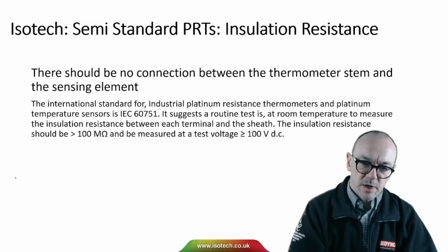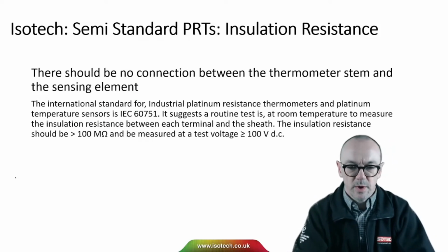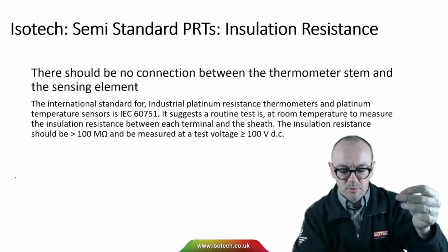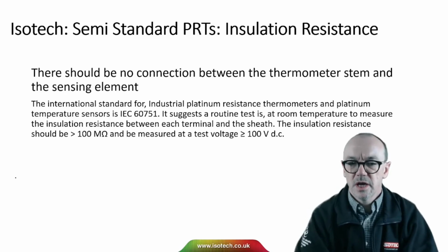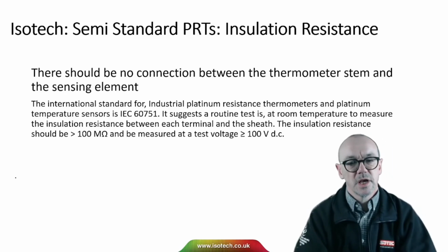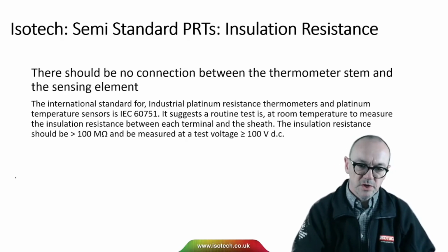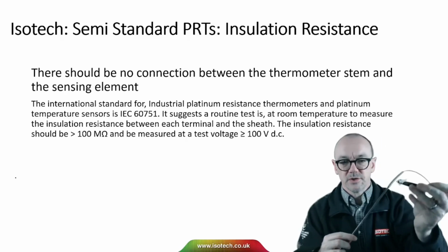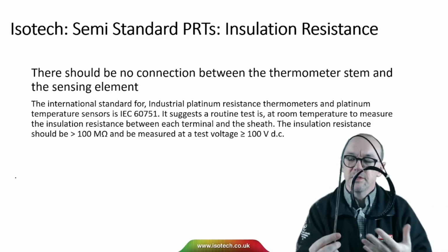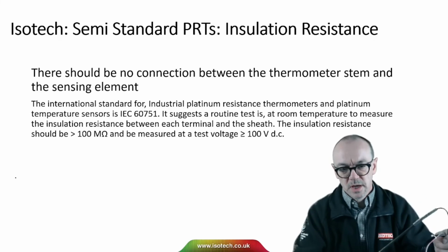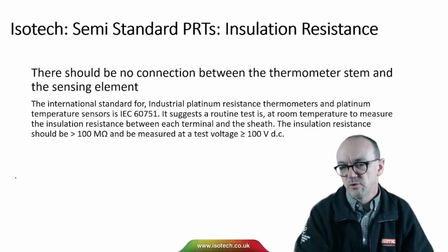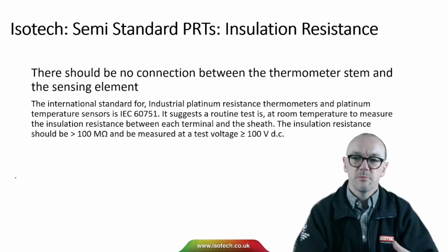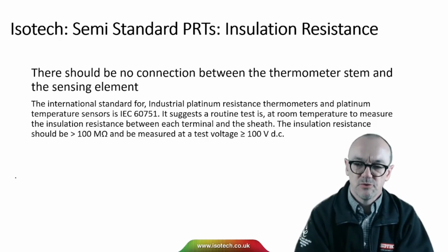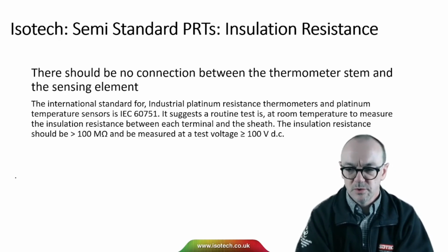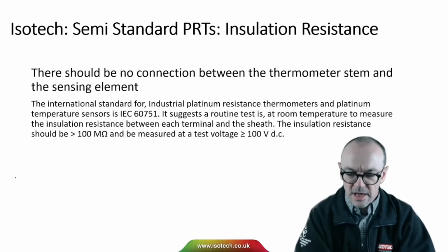With a semi-standard PRT, there should be no connection between this thermo element, the RTD, and the thermometer stem. So the international standard, IEC 60751, says routine test is at room temperature to measure the insulation resistance between the terminals or the wires of the PRT and the stem. And that insulation resistance should be greater than 100 megohms, and you should measure it at a test voltage greater than or equal to 100 volts DC. So the sort of instrument you need for that is more of a general purpose electrical insulation meter, not really a metrology instrument, but more a lower cost simple device designed to measure insulation resistance at raised voltages.